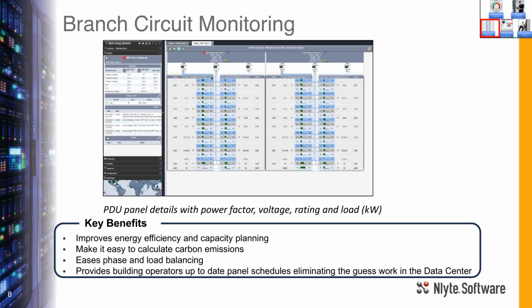So the third use case we wanted to discuss is branch circuit monitoring, which enables macro level monitoring and tracking of energy usage by measuring real-time circuit breaker utilization, while being able to monitor down to the individual PDU panels. Nlyte uses some pretty sophisticated algorithms to calculate specific system utilization metrics, such as PUE, as I mentioned before.